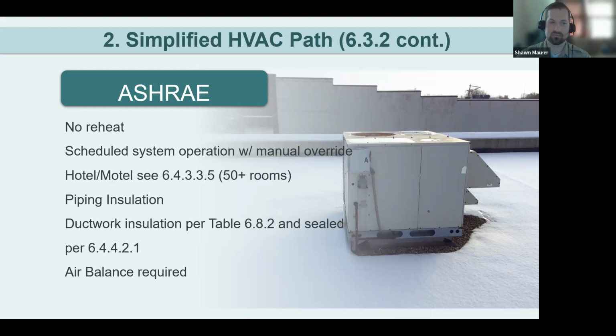Many of these are good practice. So looking at not having reheat on the system, so you're not having to deal with simultaneous heating and cooling. The system has to be properly scheduled. For hotel/motels, there are guest room requirements. Piping still has to be insulated, things like that. These are all just general good practice requirements that the simplified path is working you through. And again, it's just separating them out into an easy to follow pathway.